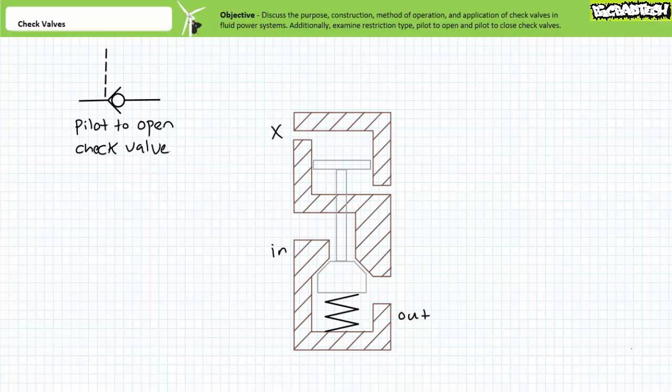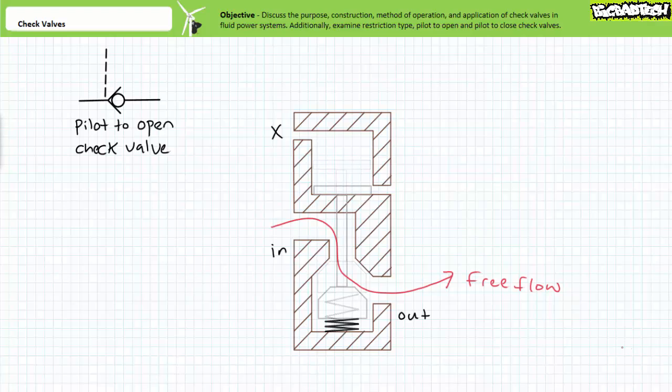The cutaway view shows the cap end of a piston receiving the pilot signal X. The piston is linked to the check valve poppet via a connecting rod. Note in this configuration, the primary passage and pilot sections are not connected, but only interact via the connecting rod.